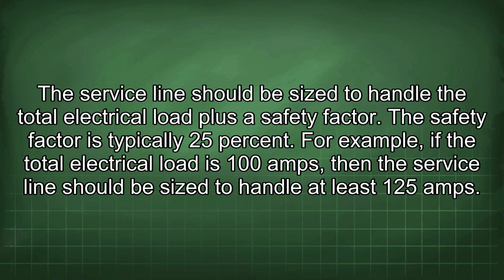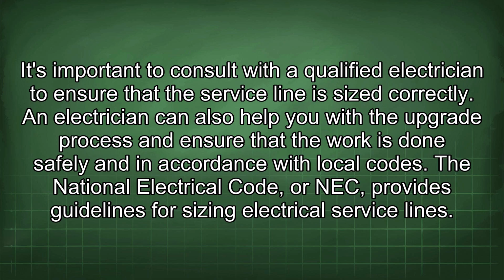For example, if the total electrical load is 100 amps, then the service line should be sized to handle at least 125 amps. It's important to consult with a qualified electrician to ensure that the service line is sized correctly. An electrician can also help you with the upgrade process and ensure that the work is done safely and in accordance with local codes. The National Electrical Code, or NEC, provides guidelines for sizing electrical service lines.